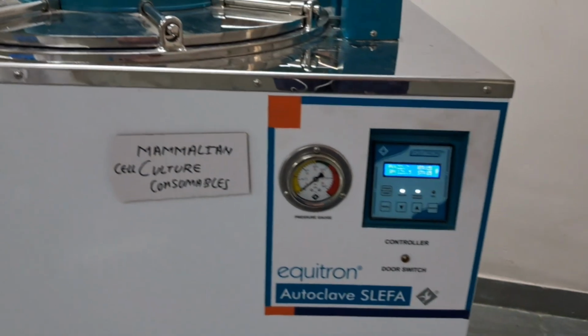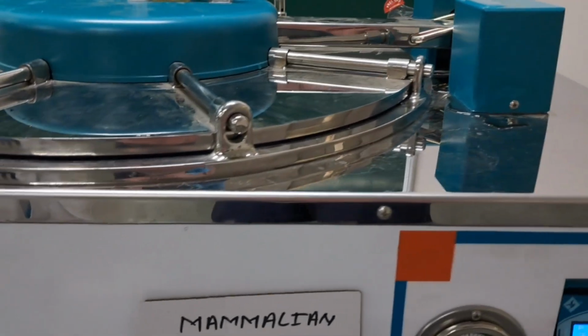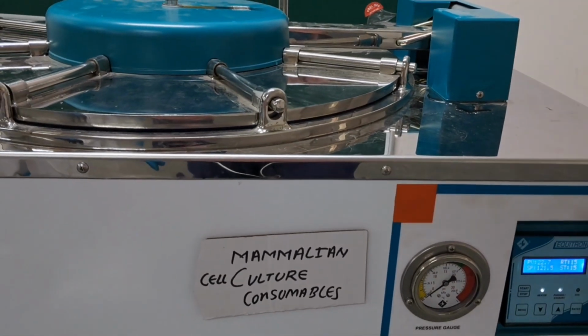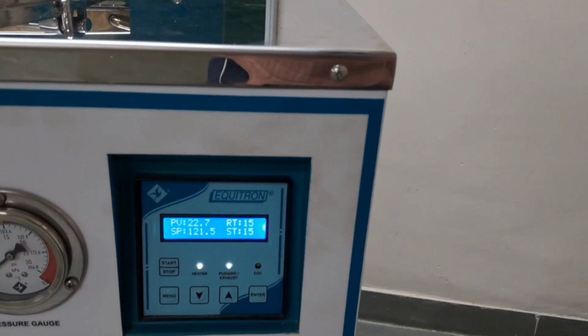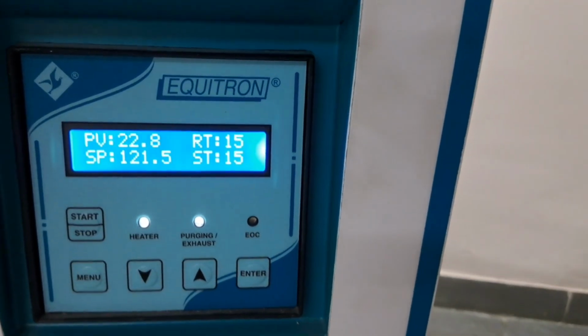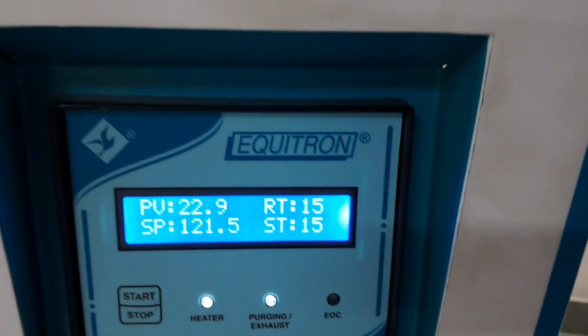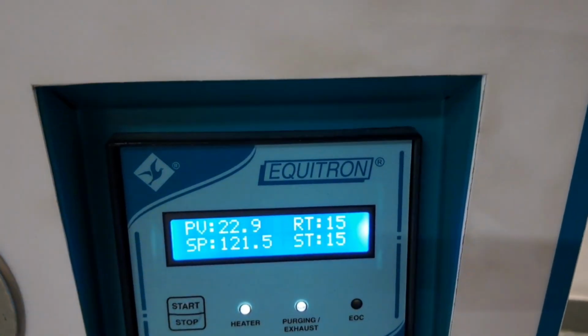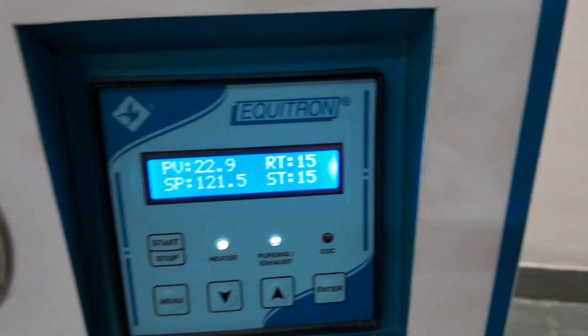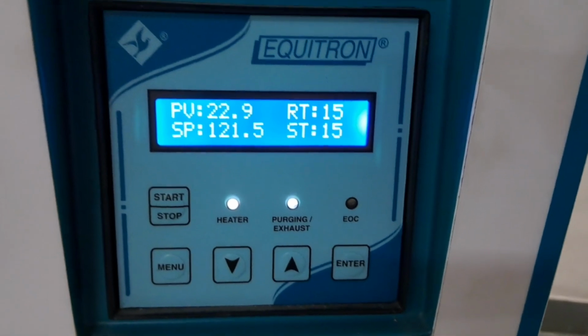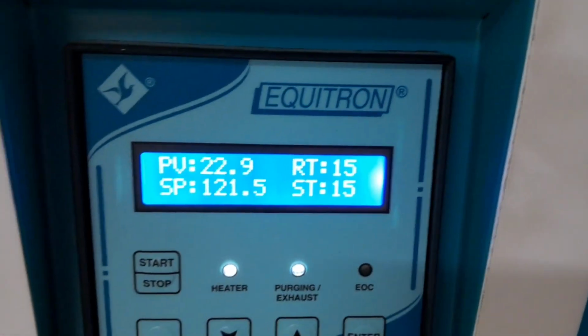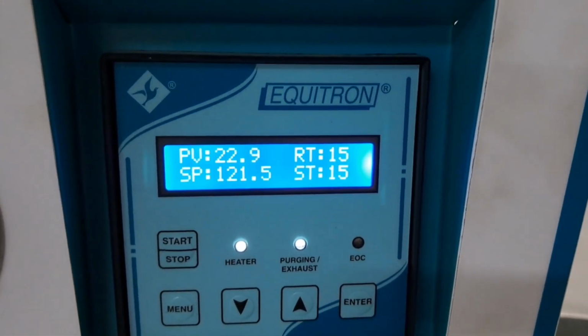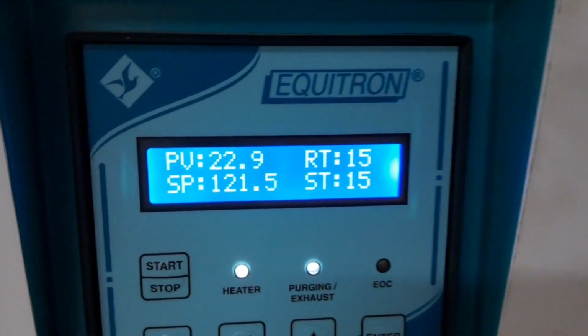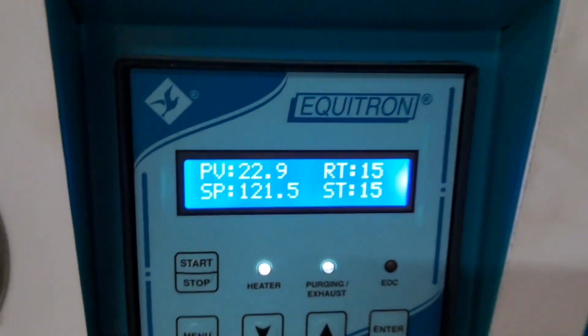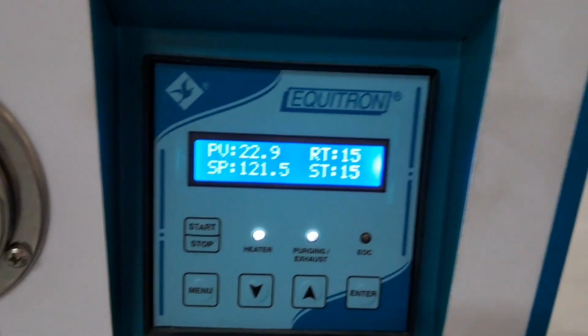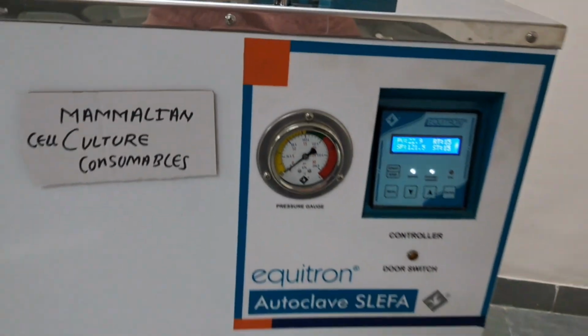And after this cycle completes, you can take it out. One thing I wanted to tell you, never open this autoclave when the PV temperature is 98 or 95, because below that you can open. It is even better to open it at 70, because the pressure will be very high, and the steam can come out, and an accident can happen.